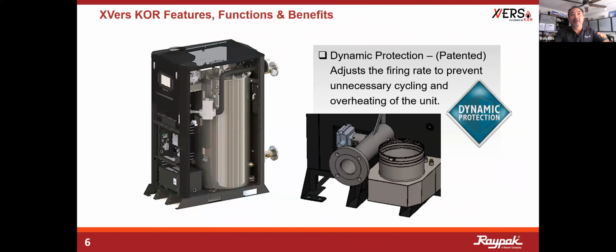Now, having said that, I mentioned dynamic protection. Why is that important? It's so important because we're trying to protect this very expensive heat exchanger. Stainless steel would seem impervious to anything. It's like it should never fail. However, there are some chemical vulnerabilities to it. However, the primary vulnerability to this heat exchanger in a hydronic system is going to be the heat stresses, and that's something that people a lot of times don't think about.